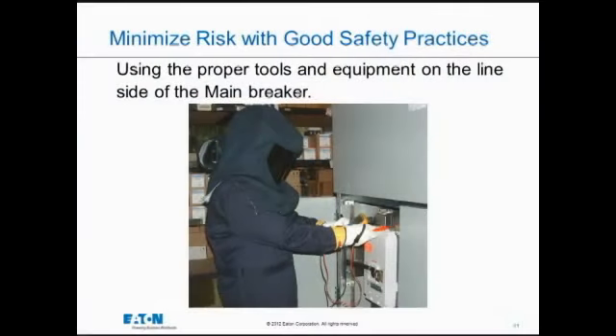This is a picture of a person at the line side of a main breaker. And at the line side of the main breaker, the hazard is much higher there. So any service entrance equipment, generally that's the bad spot in the power system for arc flash hazard, because the reason for that is the currents are generally higher.